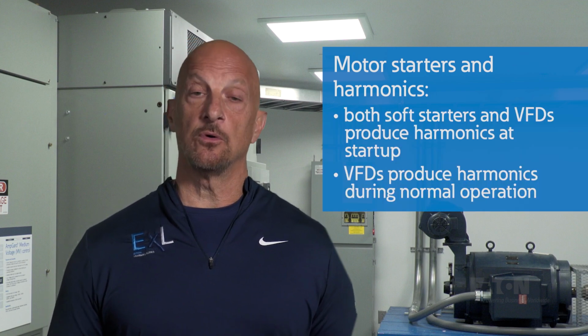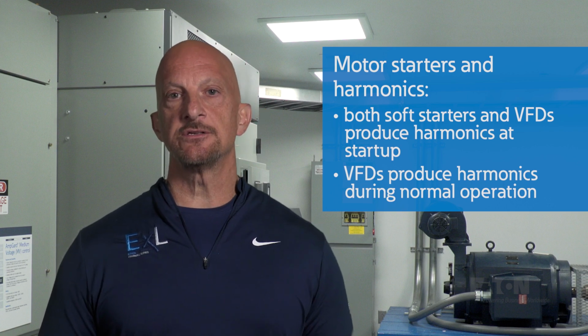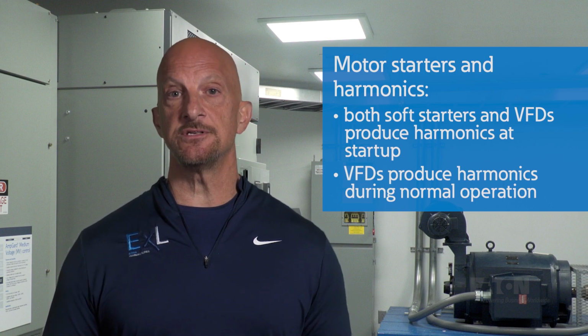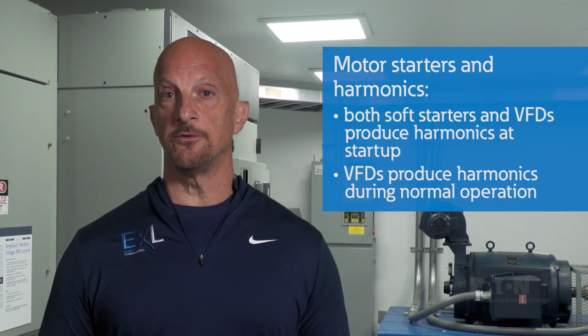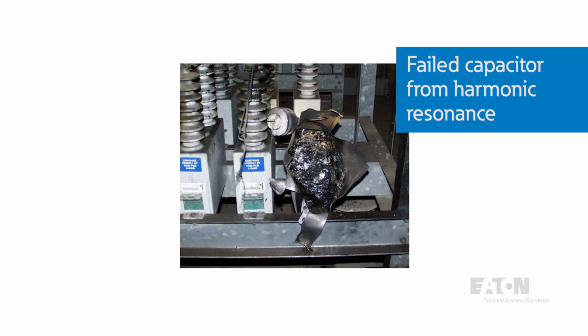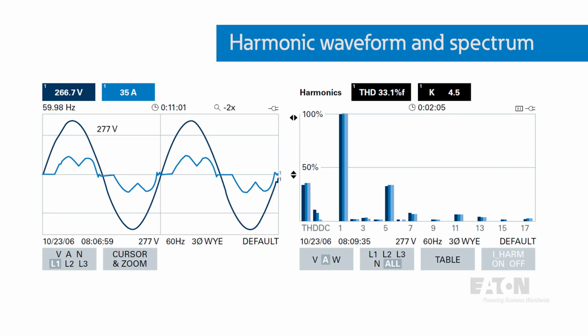VFDs and soft starters produce harmonic currents during starting of the motor. VFDs also produce harmonics during normal operation. In both cases, harmonics should be considered from a system standpoint to make sure these currents don't corrupt the voltage and interact with power factor correction capacitors on the system. Many people recognize the existence of harmonics from a VFD, but often do not recognize that they're also produced with soft starters. This is usually only a resonance problem and not a long-term heating problem, since the harmonics only exist for a few seconds that it takes to start the motor.